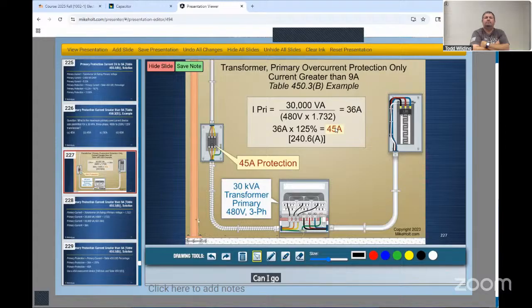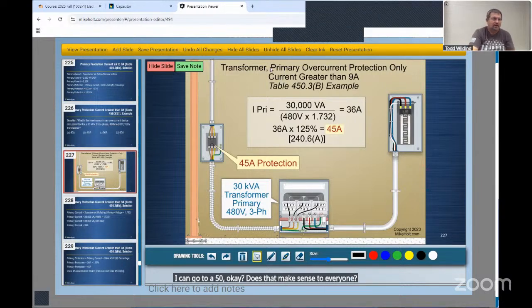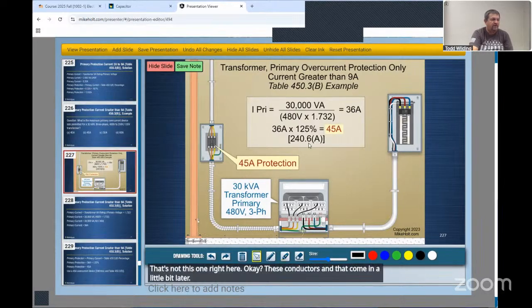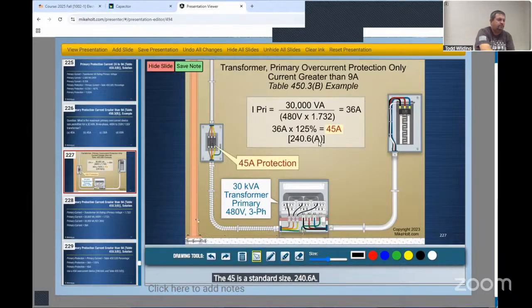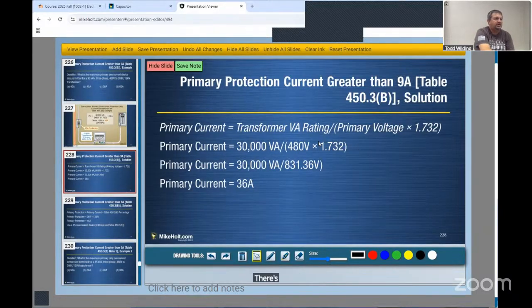Can I go up? I can now. So what size would I use if it was 46.5? I can go to a 50. Okay. Does that make sense to everyone? Again, this is just my primary protection right here. That's not this one right here. Okay. These conductors and that come in a little bit later. The 45 is a standard size, 240.6(A). There, just showing you it again.